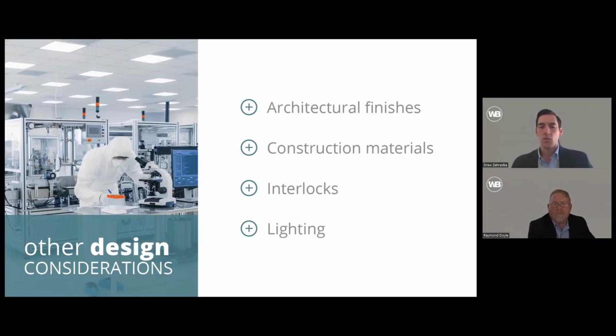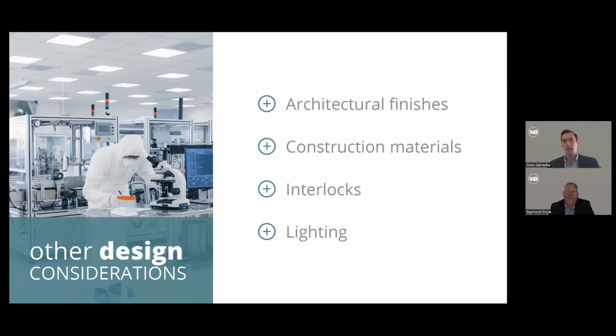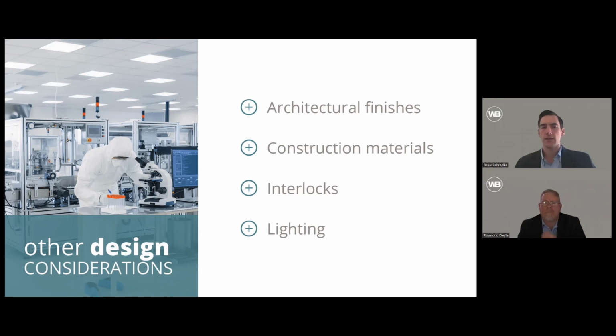And what that could lead to is, if you need to increase the amount of HEPA filters in the room, you might have to put in a teardrop light, which will sit on the ceiling grid, versus having a sealed gasketed 2x4 that sits within the grid. And those design considerations take into account total room size and air changes needed.